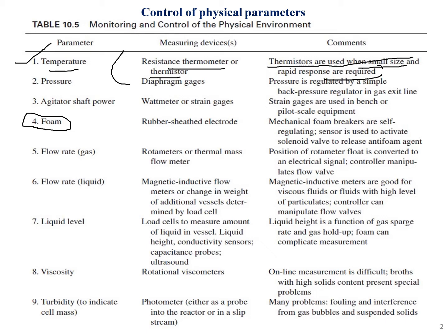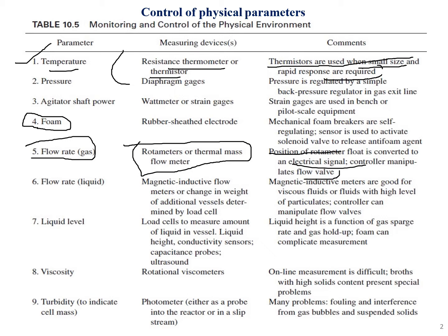The fifth point is flow rate for gas. It is measured with the help of rotameters or thermal mass flow meters. The position of the rotameter float is converted to an electric signal and the controller manipulates the flow valve.